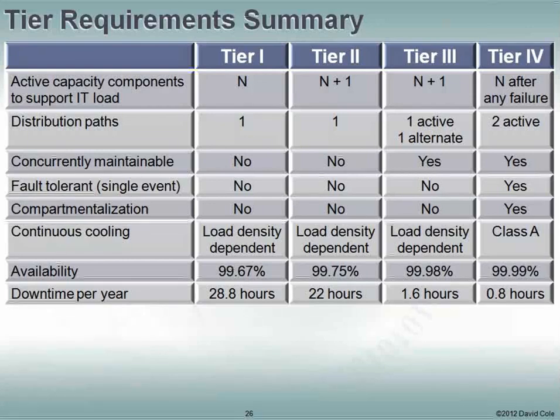Most importantly, when we get to tiering, let's look at availability and downtime. Tiering is all about availability and how much downtime we have per year. Looking at downtime per year, Tier 1 shows 28.8 hours of downtime—that doesn't mean you'll always have exactly that, you may have a whole year with no downtime, but on average you're looking at close to 30 hours of downtime per year due to planned and unplanned events.